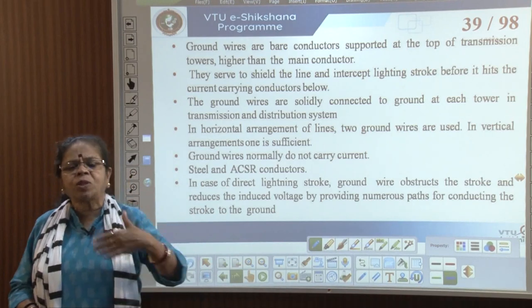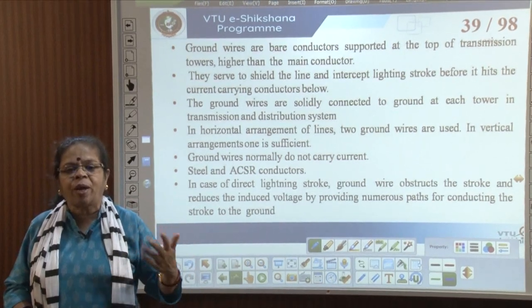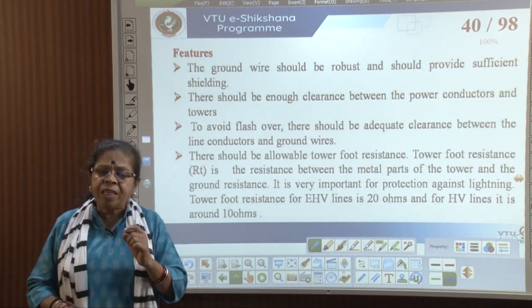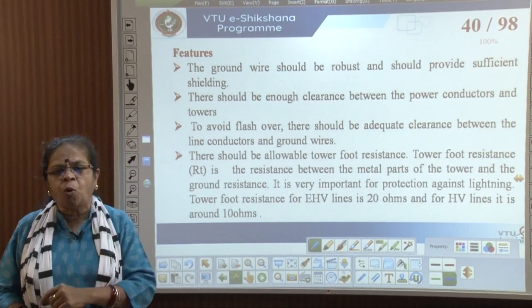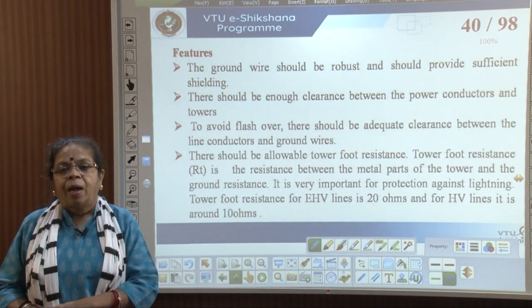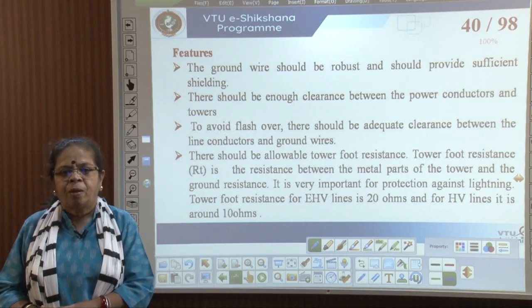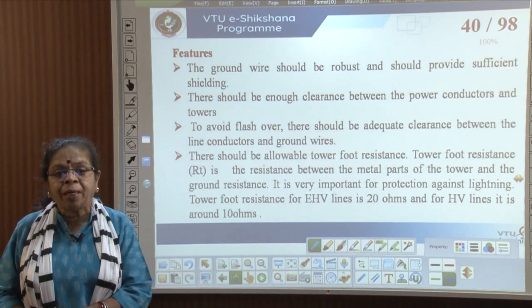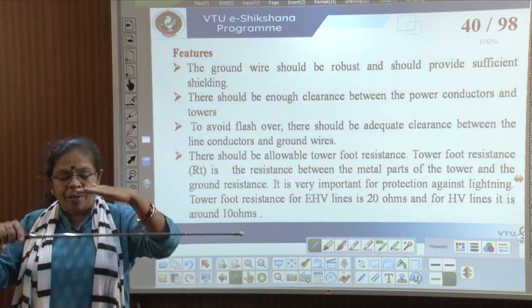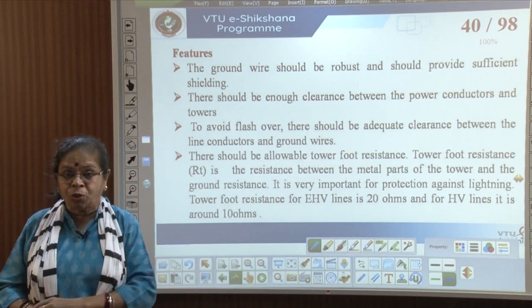Normally when lightning occurs, the strokes are repeated — there is a leader stroke followed by a number of smaller strokes striking one after another. The ground wire must be robust and capable of providing sufficient shielding. There should be enough clearance between the power conductors and the towers, and adequate clearance between the line conductors and the ground wire — otherwise a flashover can occur between the ground wire and the line wire.